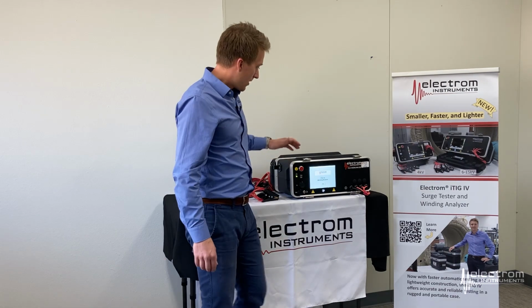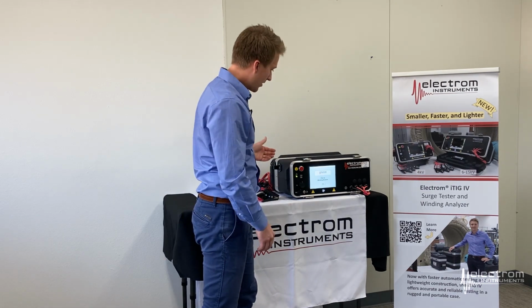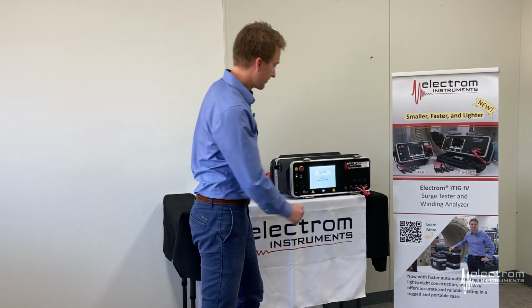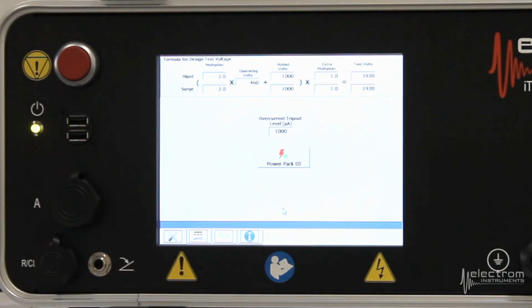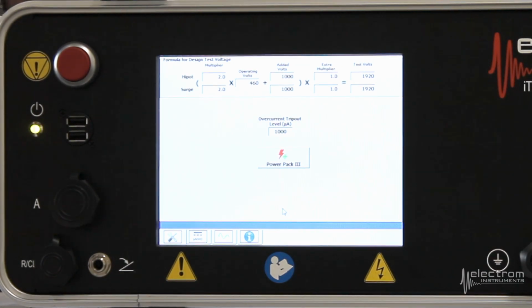So on the tester, powered on, software comes up automatically. Click start, and we get to our setup screen. At the top of the screen here you see the Hipot and surge test voltage formula. The default will be 2 times the operating voltage plus 1000.